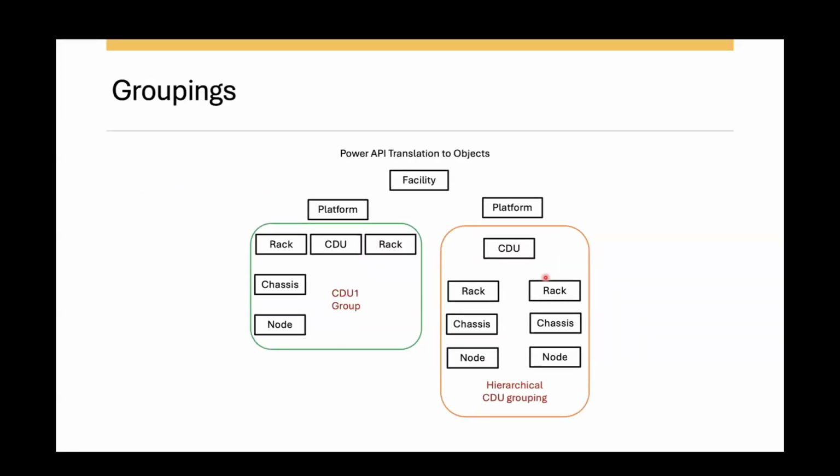And the answer is, for groups like these and for CDU interdependencies, your individual implementation can provide those groups from time t=0 when you initialize the PowerAPI interface. So there will be some groups that exist for you that are provided, things like these cooling groups, so you can understand how the system works as a whole. You can, of course, read tons of metadata in this system as well to fully understand what the ramifications of these groups are and why they're grouped the way they are. In addition to this, we have groupings of CDUs that would be provided as well, but you can also manage to group these things entirely yourself.